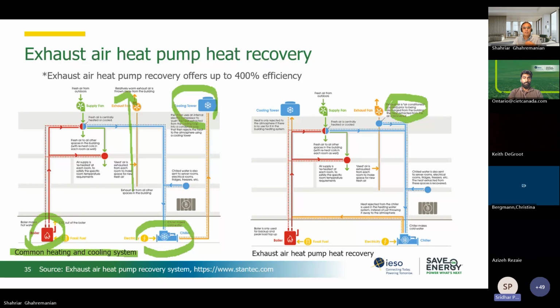Could you please explain: here the heat rejected is sent out in the boiler circuit so that it can be used for heating, but here the heat recovered from the exhaust fan is connected to the chiller on the cooling side, right? Could you explain that? Yeah, so basically we condition, I mean, the word condition, I don't like it. Let's say this is the winter season; in the exhaust fan we have heated air going through. Before that, we recover that waste heat, but in our mechanical engineering wording, we call it air conditioning. So the heat pump conditions that and converts it to whatever we wanted. But remember, it's converted to cooling.